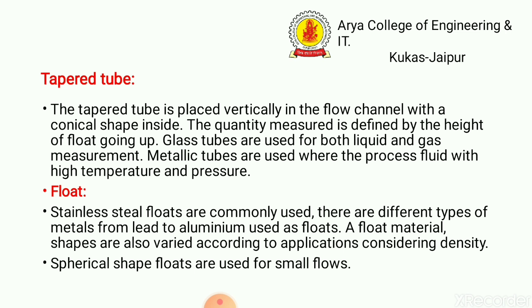The Rotometer has two components: one is the tapered tube and the other is the float. The taper tube is placed vertically in the flow channel with a conical shape inside. The quantity measured is defined by the height the float rises. Glass tubes are used for both liquid and gas measurements. Metallic tubes are used where the processed fluid is at high temperature and pressure.